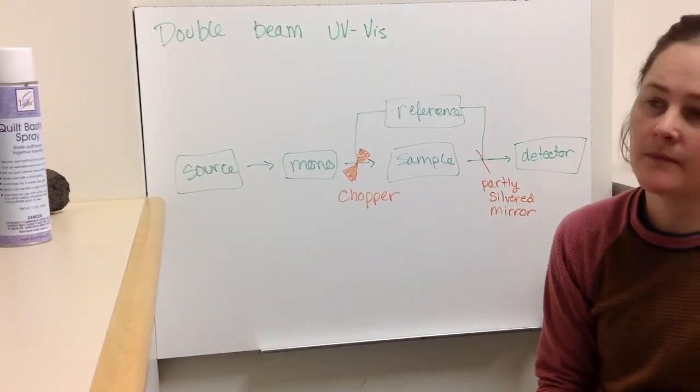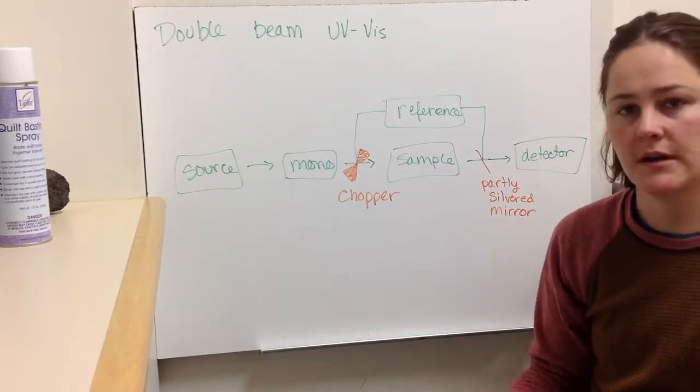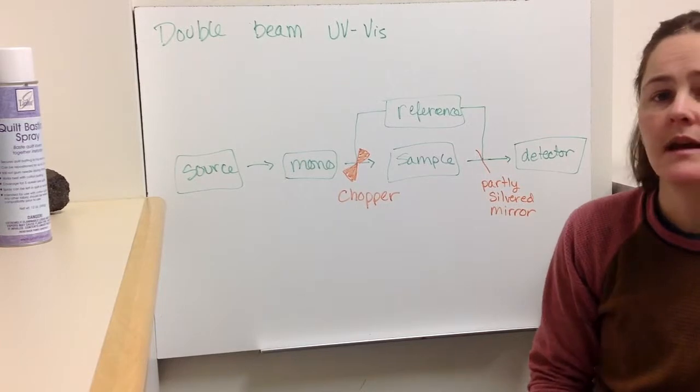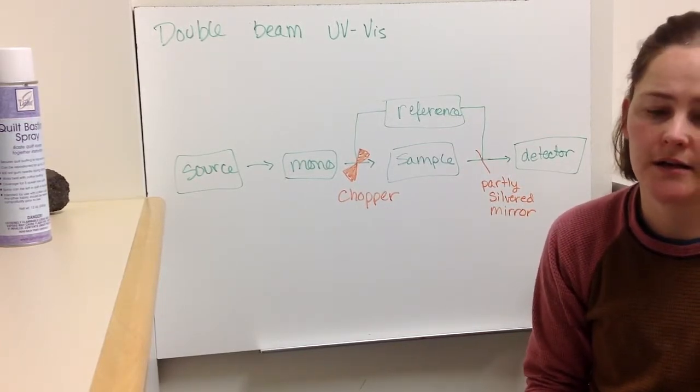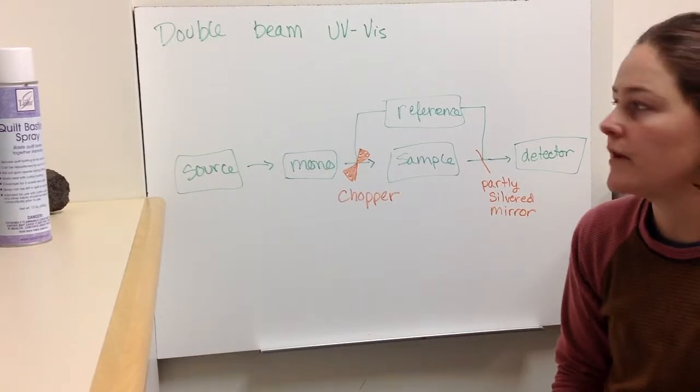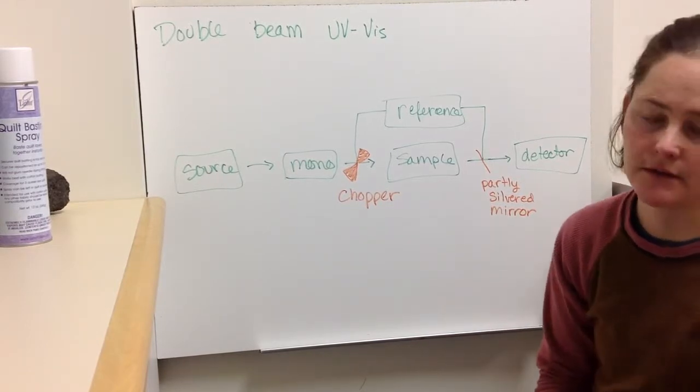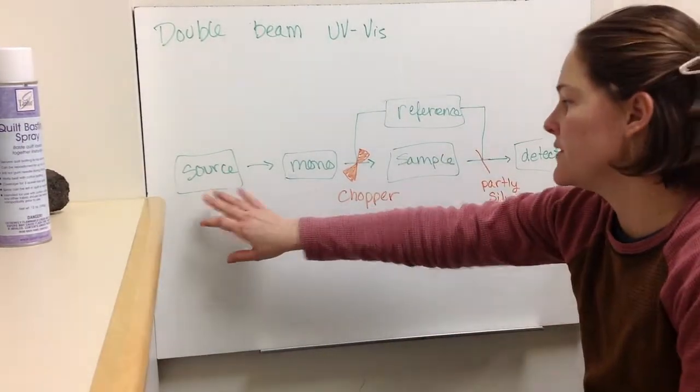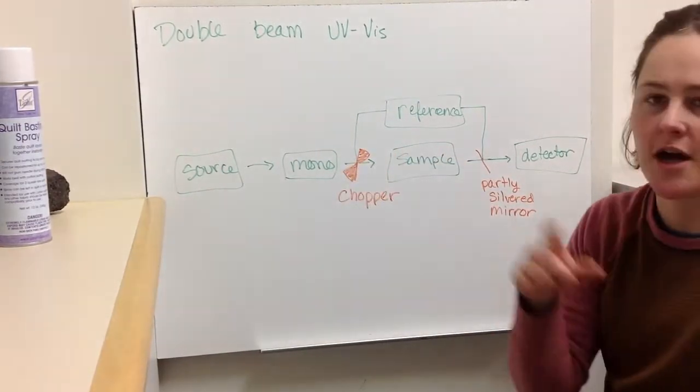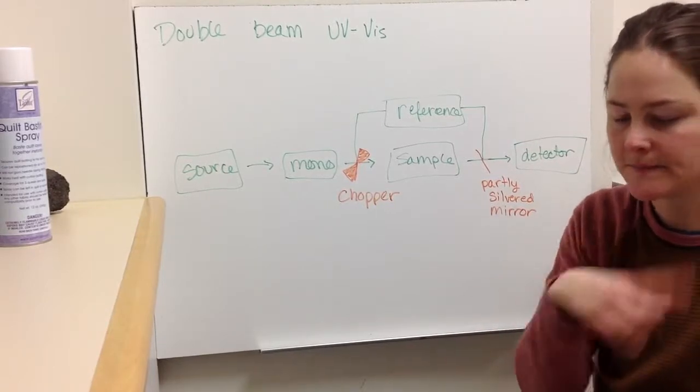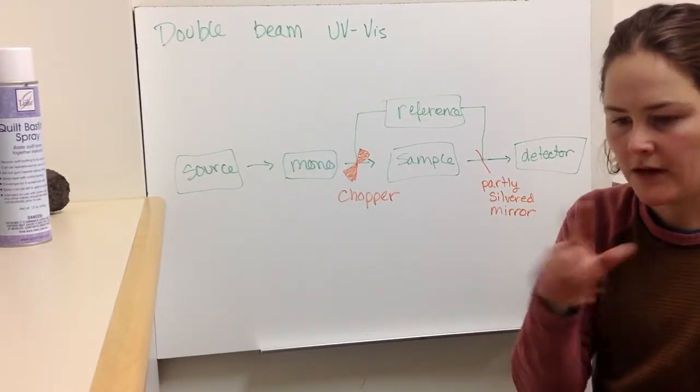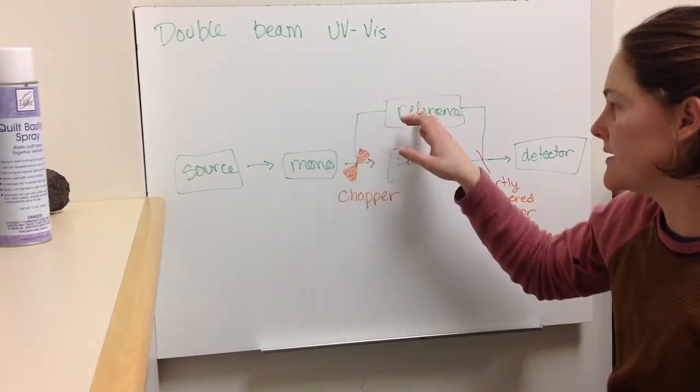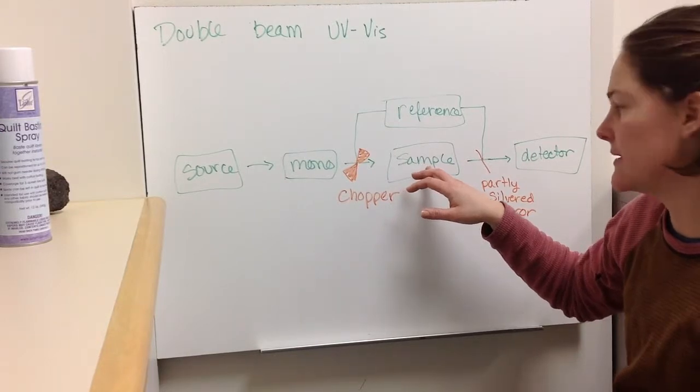So the first block diagram of an instrument was a little bit simplistic because if you want to have really good reproducibility, and you want to have the lowest signal noise possible, you want to do something like a double beam UV-vis. So where you have the source monochromator is the same, then you would have a physical chopper that rotates through. And so part of the time the light is getting bounced off and going to the reference, and part of the time it's just going straight through, through the sample.